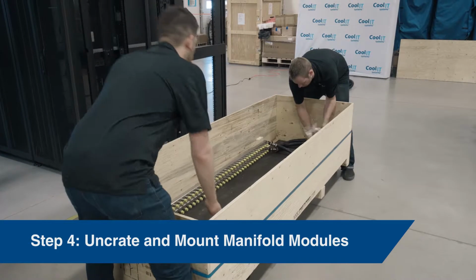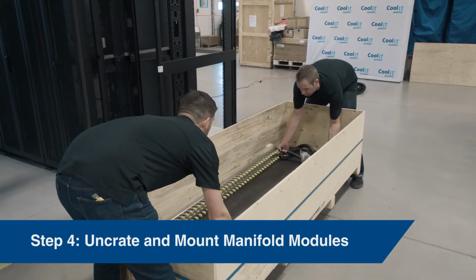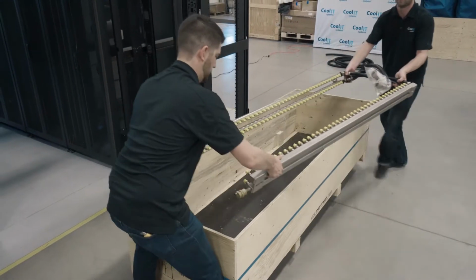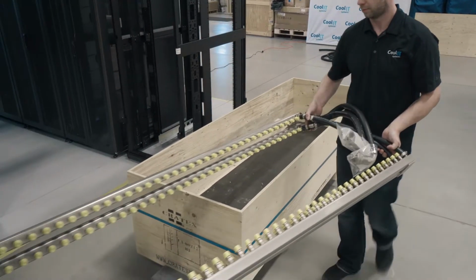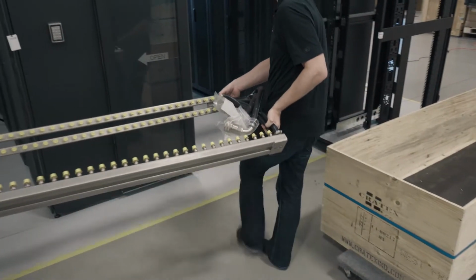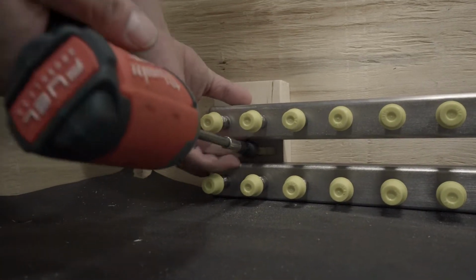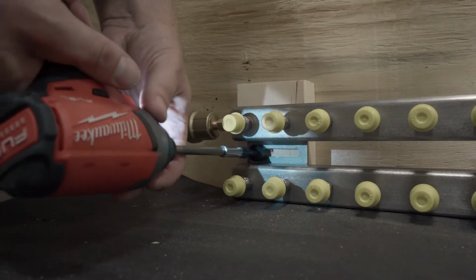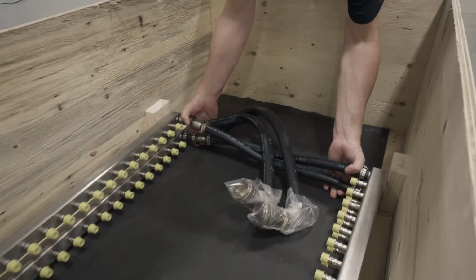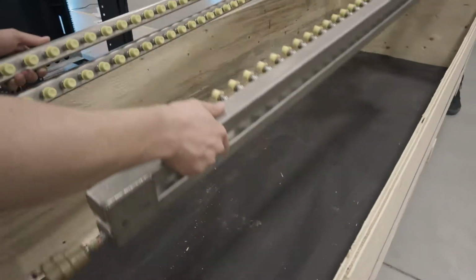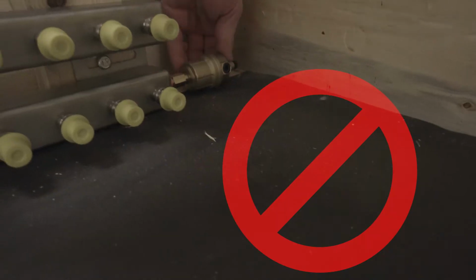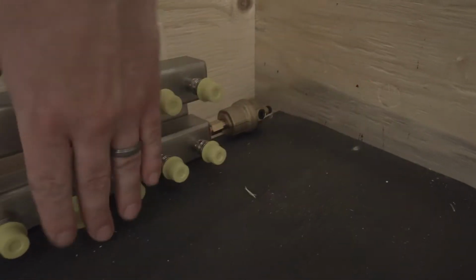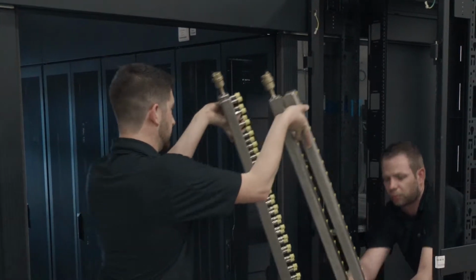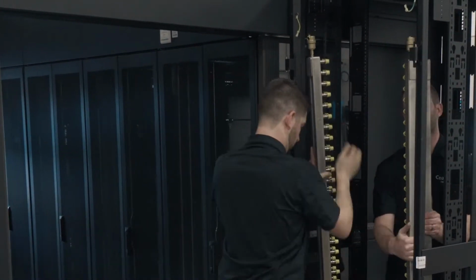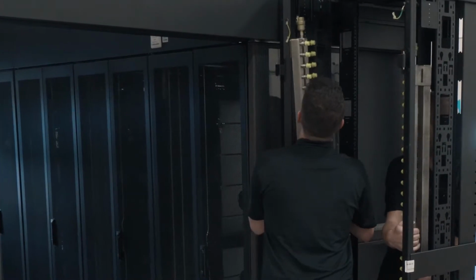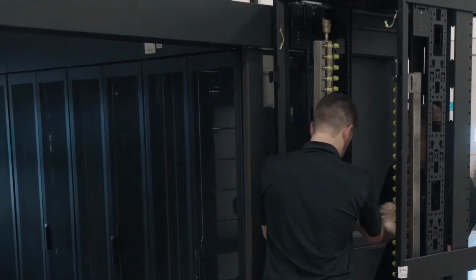Step 4. Uncrate and mount manifold modules. Removing the manifold from the crate and installing it into the rack will require 2 people due to the weight and size of the manifold. Locate and remove the bolts securing the manifold to the crate. The next step is to remove the manifold from the crate and move it to the rack. It is very important that the manifold module is not lifted by grabbing the quick disconnects or the automatic air bleed valve. Instead, grab the sides of the manifold or the tubing when moving and installing it. Make sure to replace any quick disconnect covers if they are knocked off.